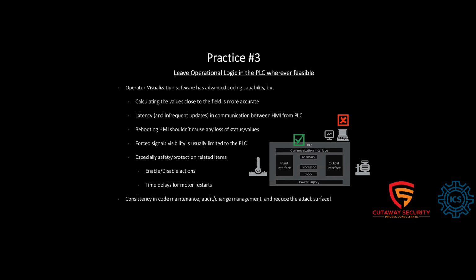Next up, another one: leave operation logic in the PLC wherever feasible. This is kind of interesting because over time, the user interface software, the operator visualization software, has become more powerful. So you can add logic in the HMI itself without touching the controller. But what we're saying in this practice is try to keep all the logic in the PLC itself and not use the HMI for it, for a few reasons. One, calculating the values closer to the field is going to be a lot more accurate, and that means the PLC, because that's connected to the IO. And then there are infrequent updates to the HMI because there is latency between the HMI and the PLC. Obviously, the PLC is runtime, whereas the HMI has maybe one per second polling as needed. So there is that latency.